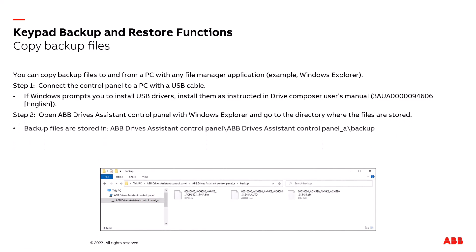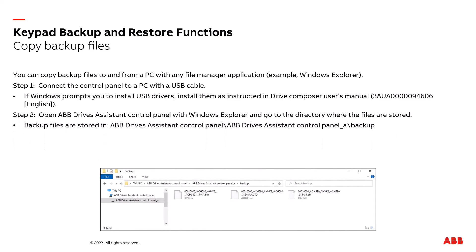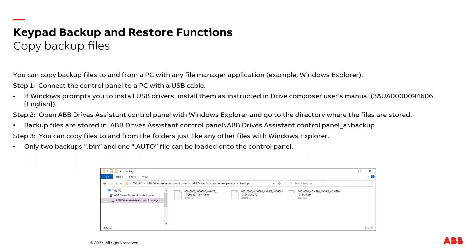Let's review copying backup files. You can copy backup files from any PC with any file manager application, such as Windows Explorer. Step one: connect the control panel to a PC with a USB cable. If Windows prompts you to install a USB driver, install as instructed in the Drive Composer user manual. Step two: open ABB Drives Assistant Control Panel with Windows Explorer and go to the directory where the files are stored. Backup files are stored in the ABB Drive Assistant Control Panel underscore A backup folder. You can copy these files just as any other file in Windows Explorer. Only two backup .bin files and one .auto file can be loaded onto a control panel.